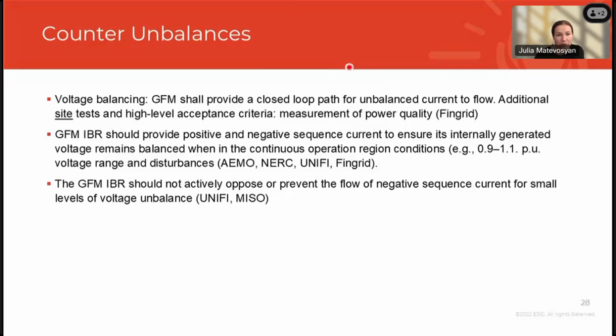Fingrid requires providing a closed loop path for imbalanced current to flow, and there are additional site tests and high level acceptance criteria when measuring power quality during the commissioning process. In other requirements, it says that grid forming should provide positive and negative sequence current to ensure that its internal voltage source is balanced during continuous normal operation and also during disturbances.